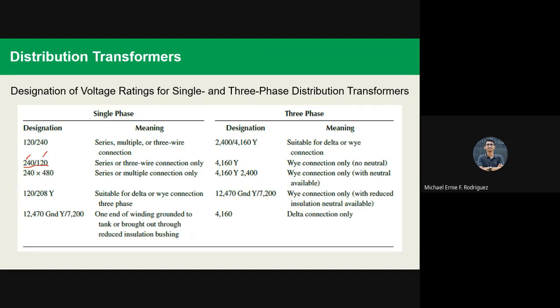So this winding is appropriate for series, multiple. Okay. Mali. Hindi yan. So ito naman sa taas. Okay. So that is appropriate for series, multiple, or three-wire connections. So it will have the designation of multiple voltage rating, followed by a slant and the series voltage rating. So meron ka ditong multiple voltage rating, then meron kang slant, tapos yung series voltage rating. So kapag series, multiple, or three-wire connection, meron kang 120 by 240. Okay? So yung 240, yan yung series voltage rating. Itong 240. And then yung 120 dito, that is your other voltage rating.